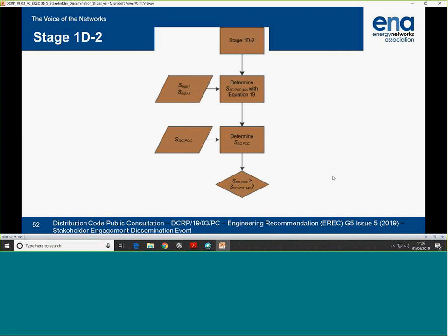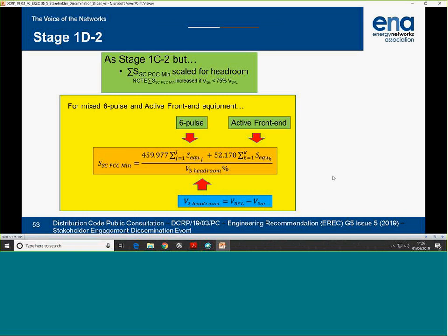1D2 comes from 1C2. So this is where you have the mixture of equipment. The equation for that is this one, and then again, you're scaling for headroom. So it's the same idea. Because we've got minimum fault level, and when you have 50% of the planning level left, the number on the bottom gets bigger, and the fault level required is then halved.